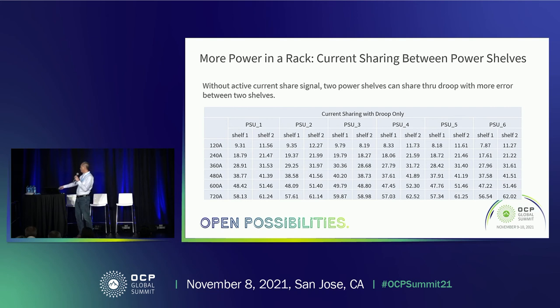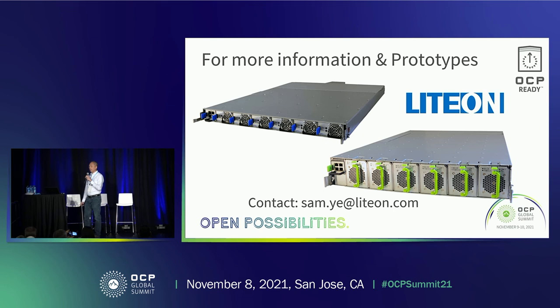The highest output is about 62 amps and the lowest is about 56.5 amps — still within a 5 to 10% difference. You are welcome to come to the LiteOn booth to see our samples. We also have a live demonstration of the system in our lab that we can remotely connect to, so you can see the transfer between the PSU and BBU. With that, we will take some questions.